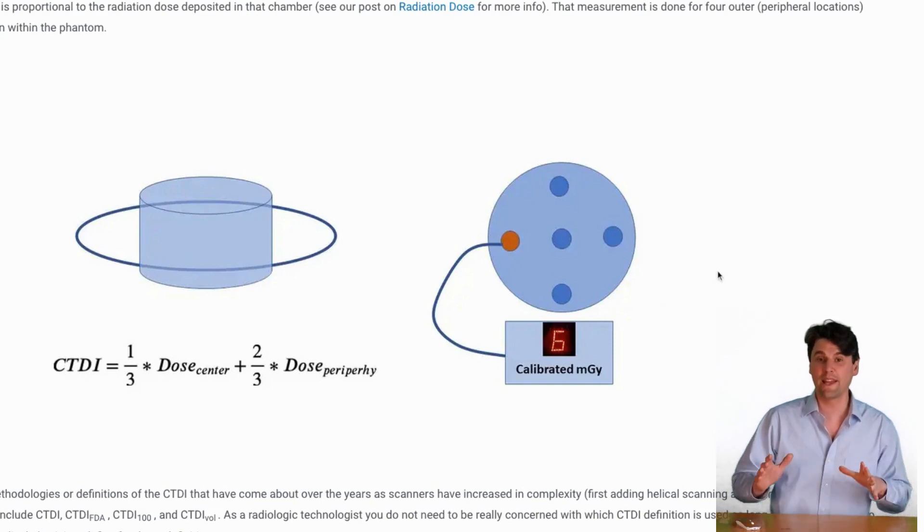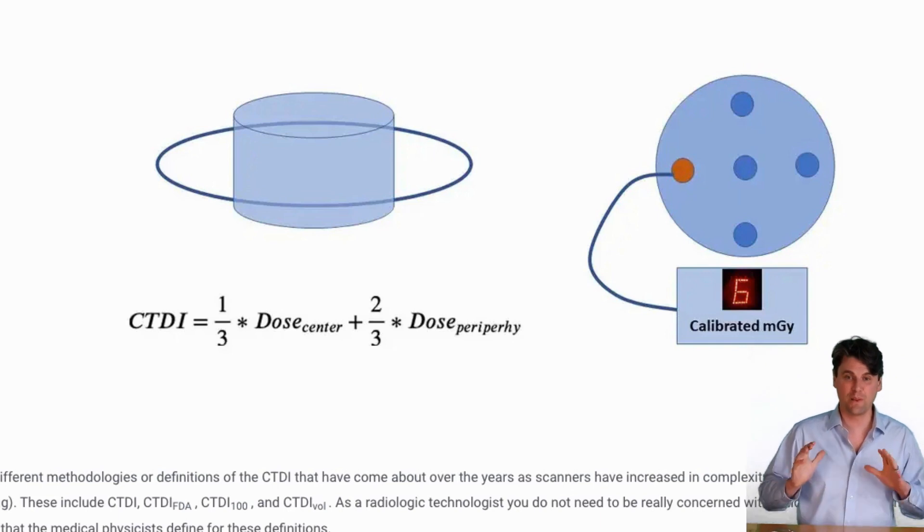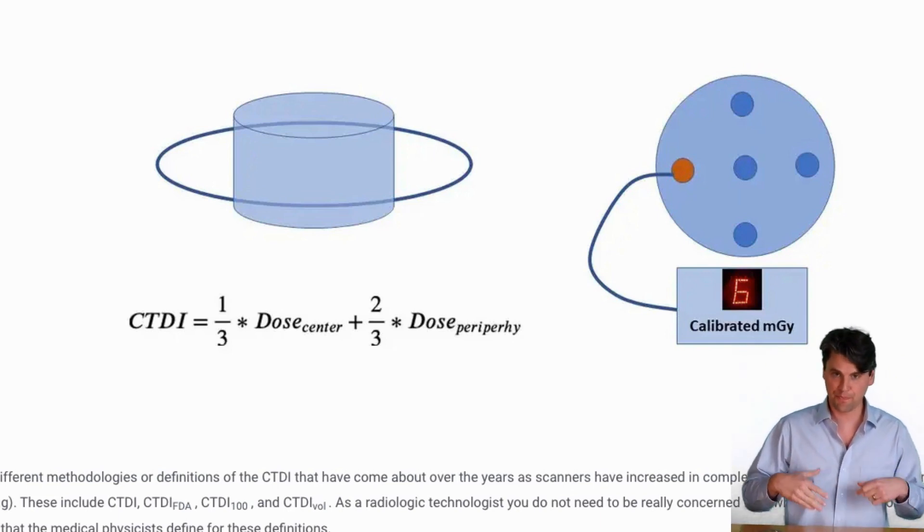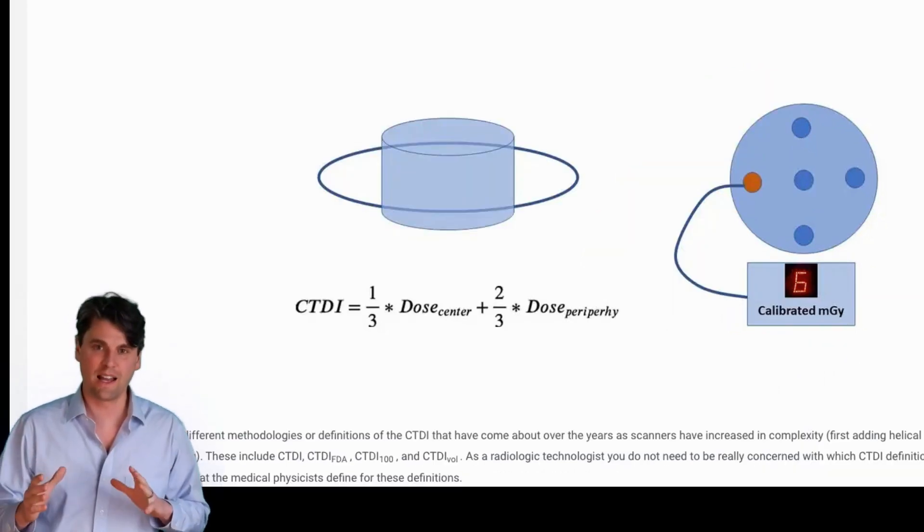The CTDI is a weighted combination of the outer measurement and the inner measurement. We call these periphery, the ones on the outside, and the one in the middle is the center measurement. It's a weighted combination between the outer and inner measurements, all made with the same ion chamber.